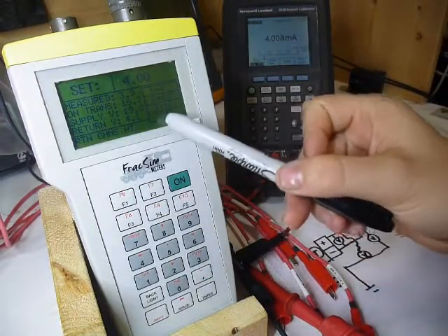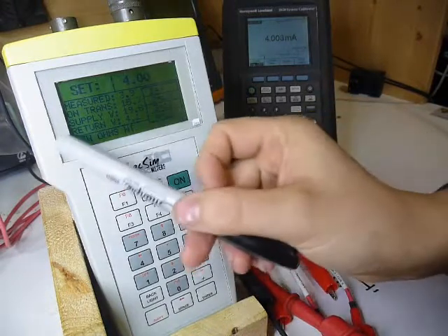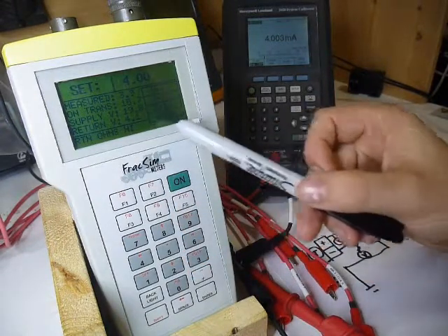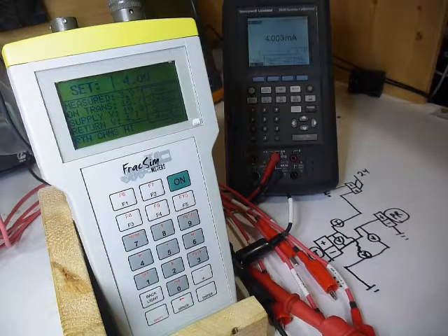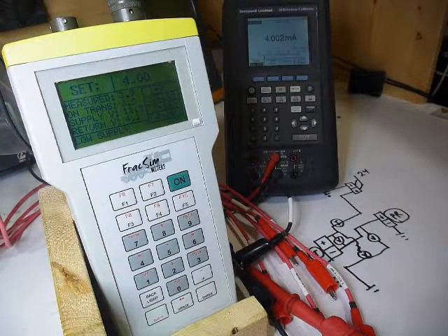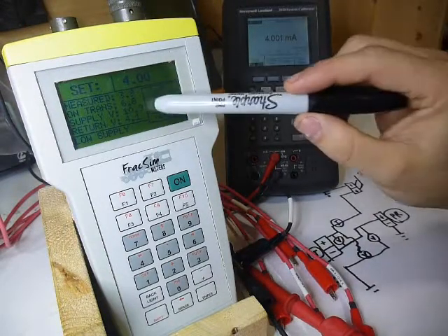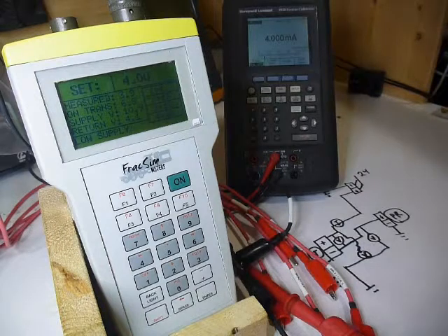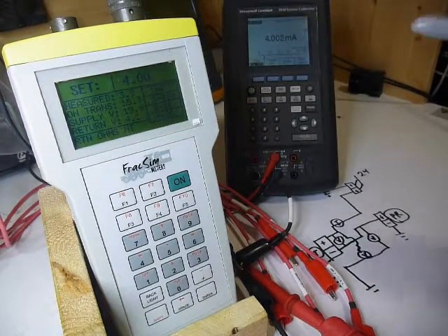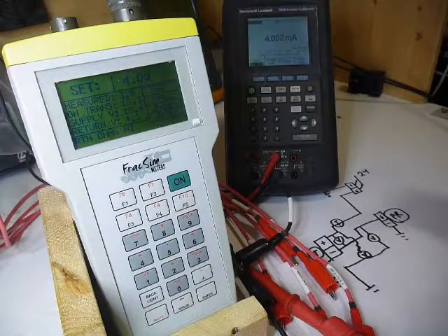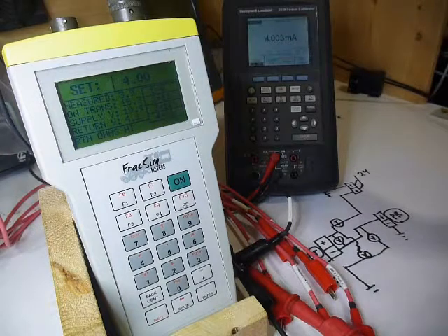And so this system, the 3-wire current sim measure, also includes these diagnostic messages at the bottom. So I can see some of the other diagnostic messages. I'm just going to turn down the loop supply. You'll see as soon as you drop below 12 volts supply voltage, it also says low supply. And if you keep dropping down right to nothing, it'll say no supply. So basically, it gives you every single measurement you could possibly need, not that you could possibly need, but most likely ever need for troubleshooting a loop.